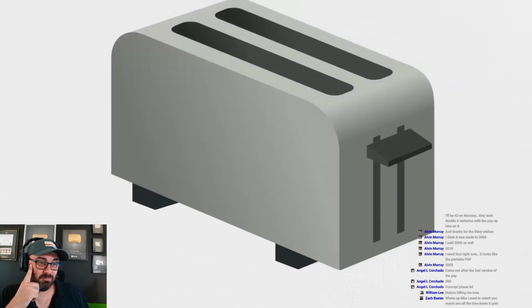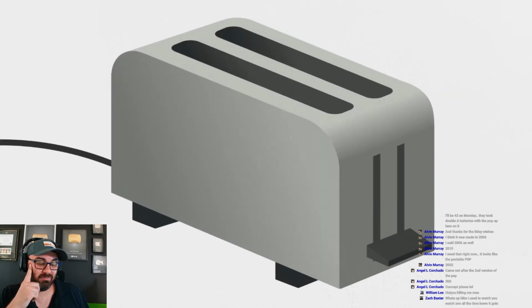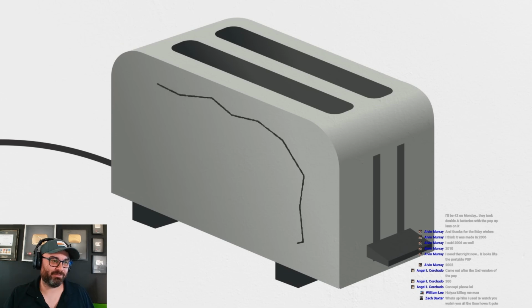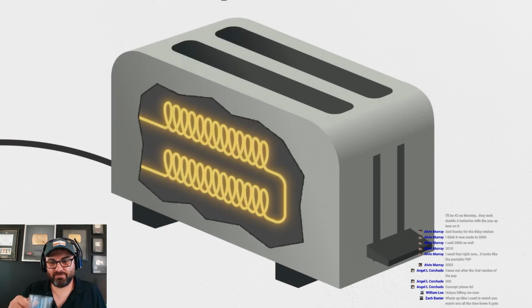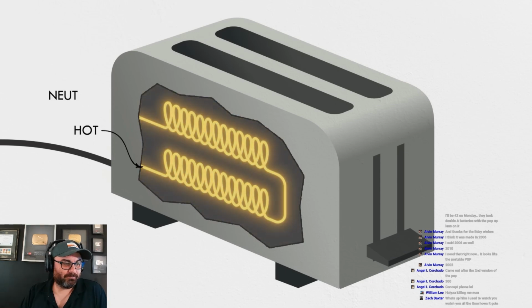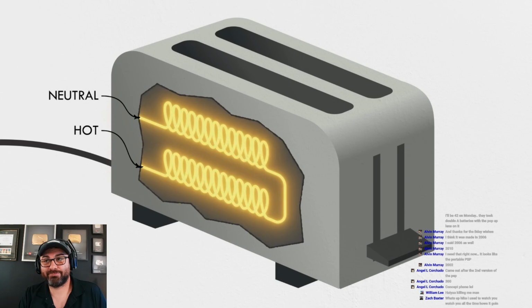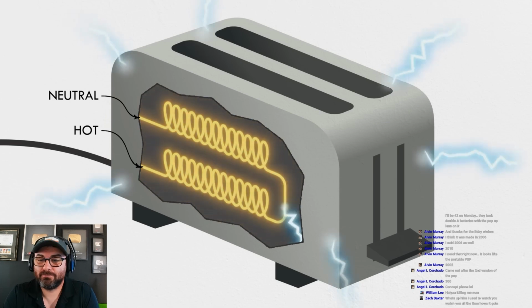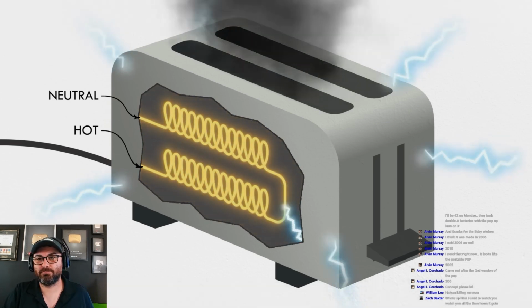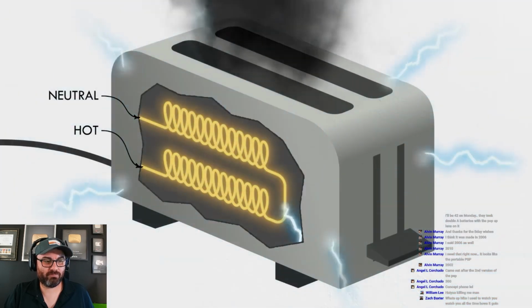If you know much about wiring in buildings, you might be familiar with the classic example of a toaster with a metal case. It could be any appliance, but let's use a toaster. Under normal conditions, current flows from the live or hot wire through a heating element and into the neutral wire to return to the grid, completing the circuit. But if something comes loose inside the toaster, the live or energized side of your electrical supply could come into contact with that metal case, making it energized too. This could start a fire or, in the worst case, shock someone who touches the case.